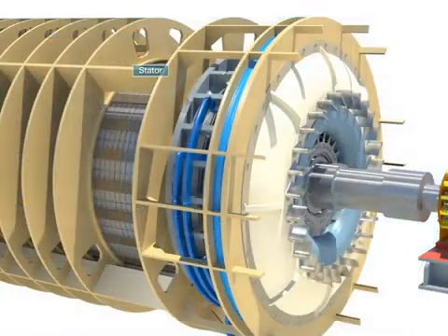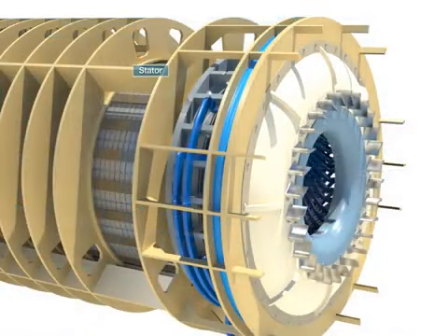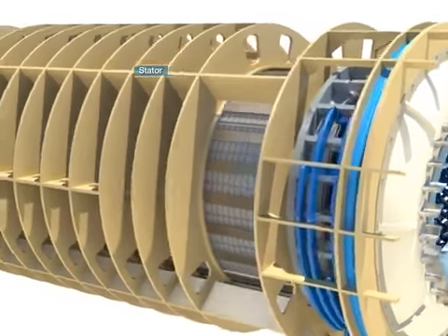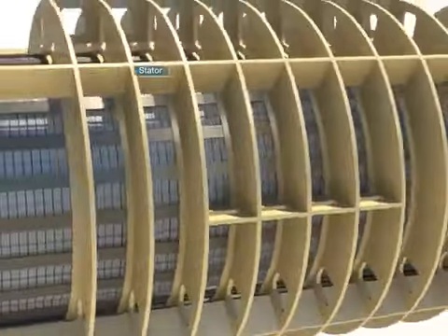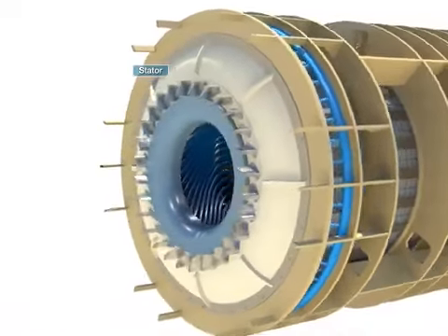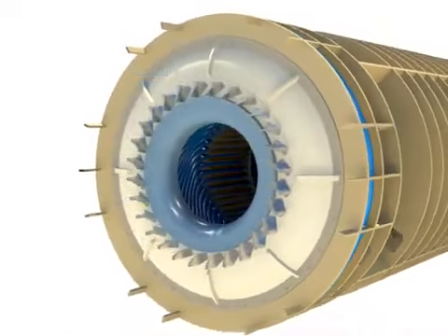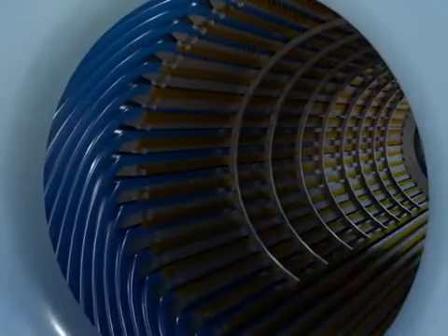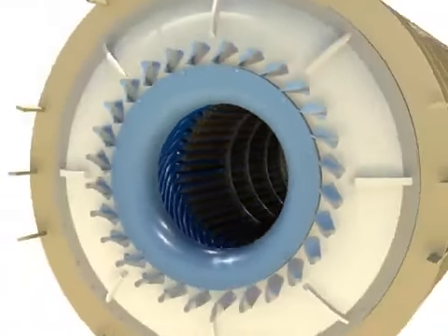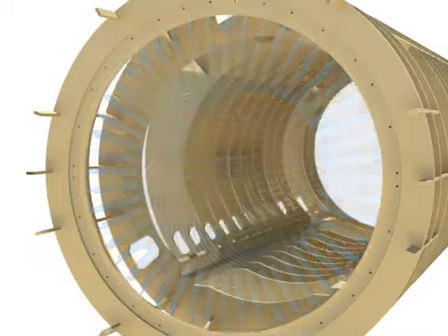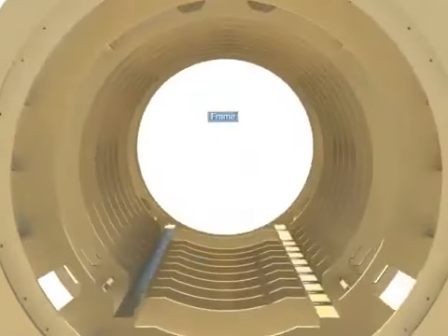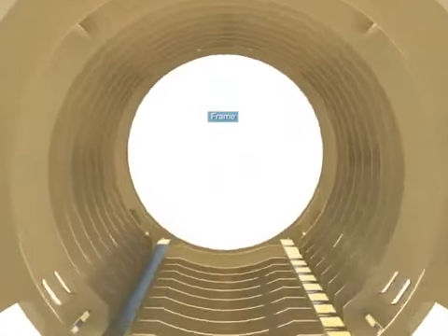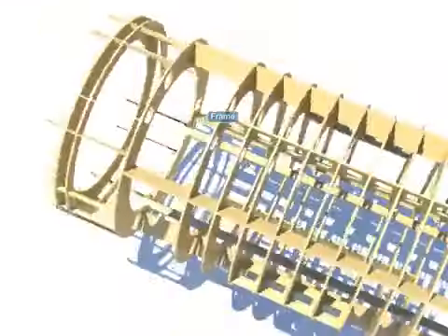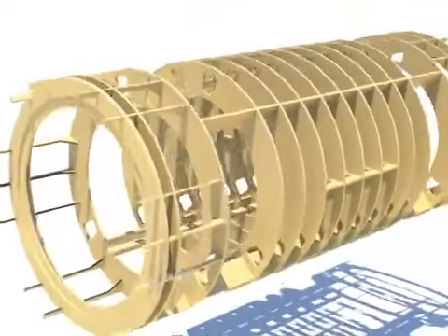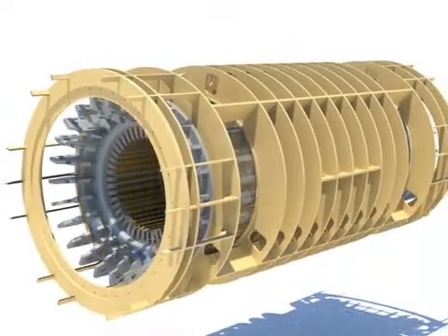The stator is a part which is fixed in a generator, and the armature winding is assembled in it and generates electromotive force by interlinking with the magnetic flux provided by the rotor. It consists of the core supporting the winding and the frame to install the core. The frame is a cylindrical structure supporting the stator structure, bearing stand, and the hydrogen cooler, which works as an attached device supporter, sealing hydrogen gas, constructing airway, and preventing torsion.